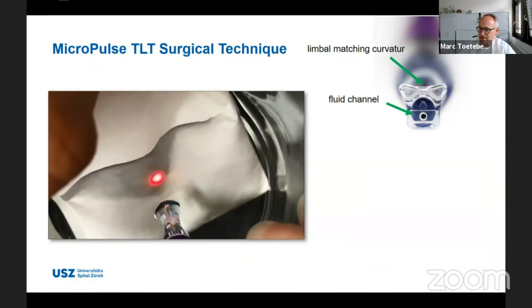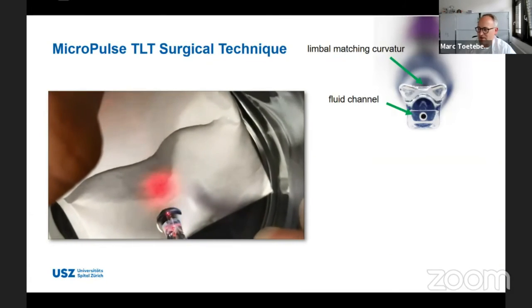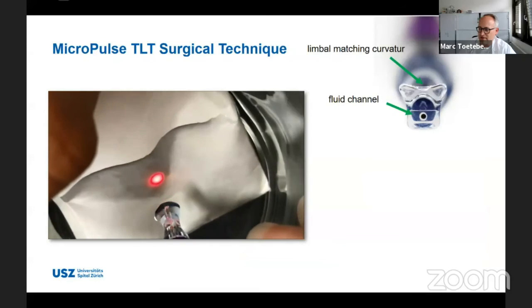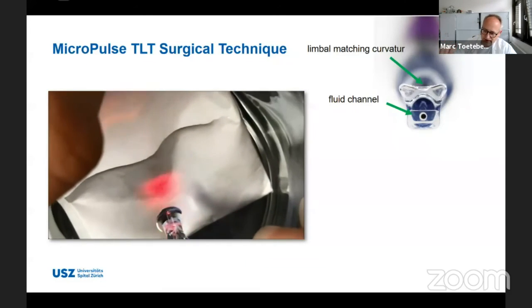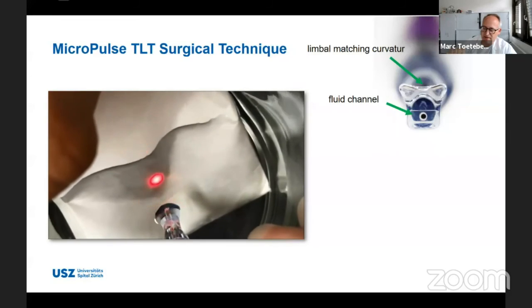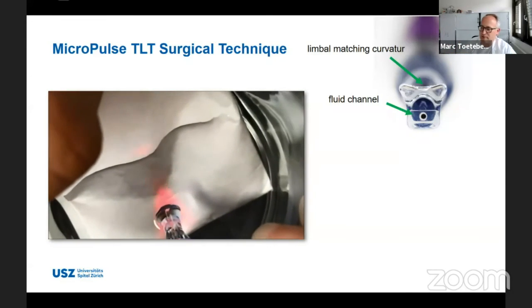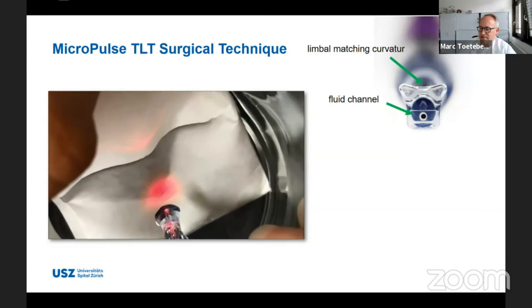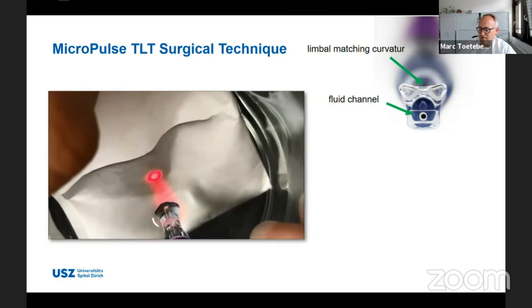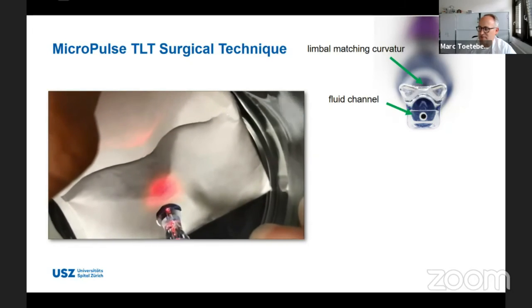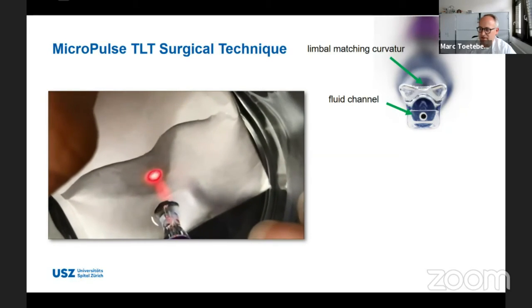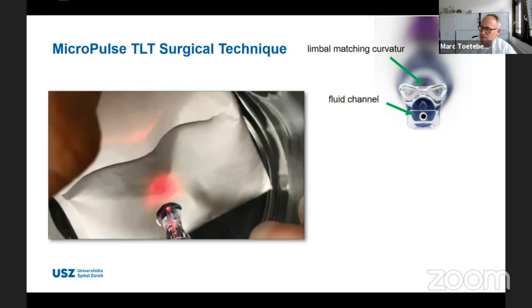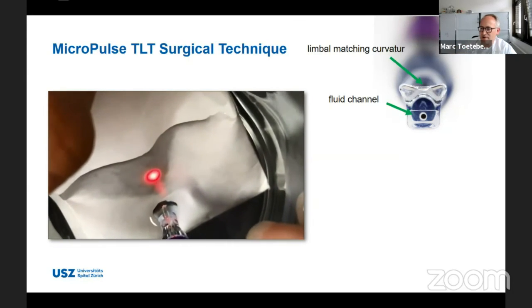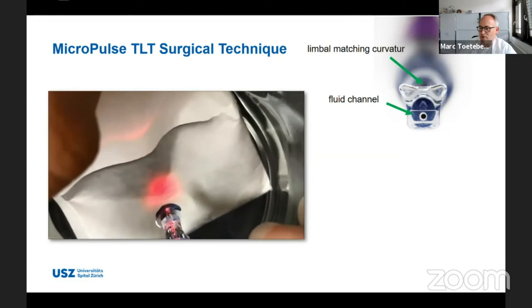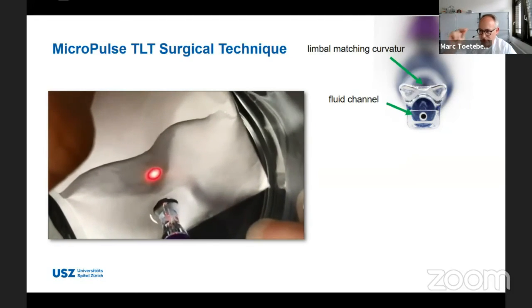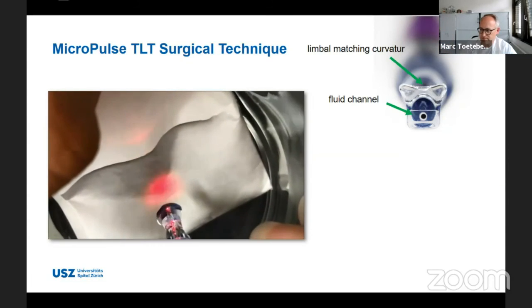And going back to the liquid interface, if you see the video on the left, that's the generation 1 hand probe. If you have it outside of water, the laser beam is spreading. If you have it inside the water, inside a liquid interface, the laser beam is nicely narrowed with parallel laser energy coming out. And that's why you should be having a liquid interface, methylcellulose, for example. And in this fluid channel, you see on the right in the foot plate, the methylcellulose will stay in, and in the middle of this fluid channel, the laser fiber is coming out of the hand probe. And that way you always have your laser energy focused on a single spot and not spread over a wide area.